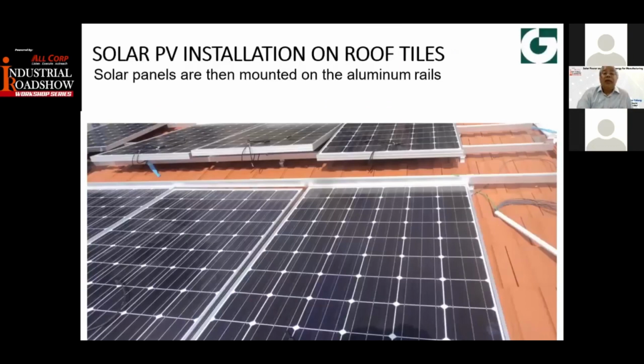But there are also cases like this. This picture is while we do the installation. We make sure all the cables are tested before we do the connection, because we want to make sure that all the modules we install are good and can work properly. So before we connect, we test the system and check the IV curve first before it is connected on the roof.